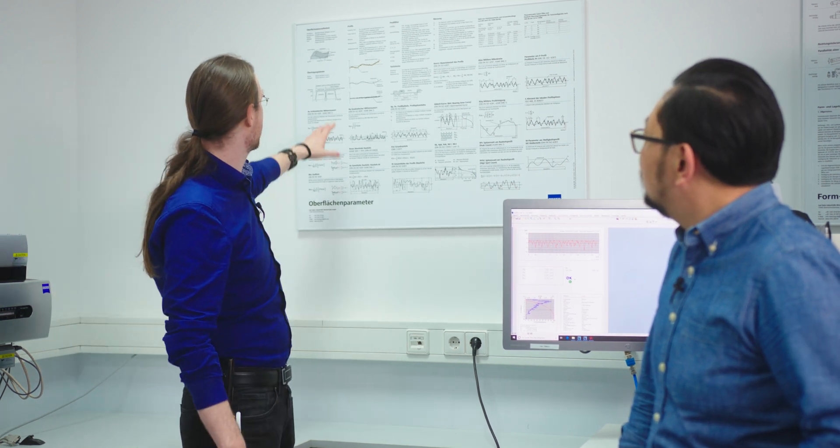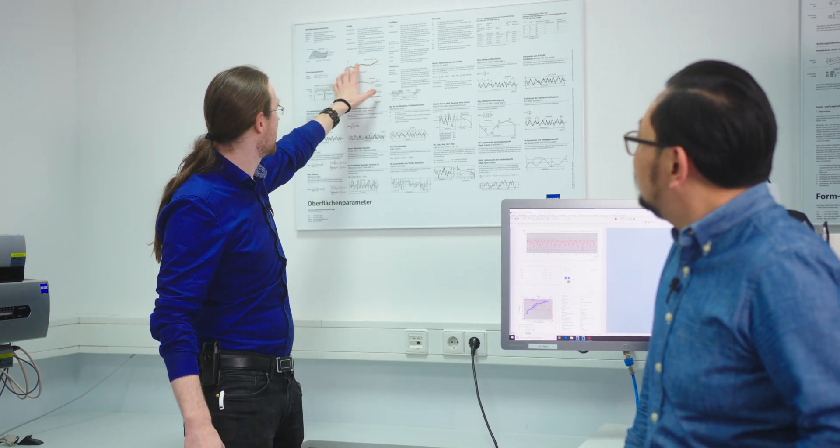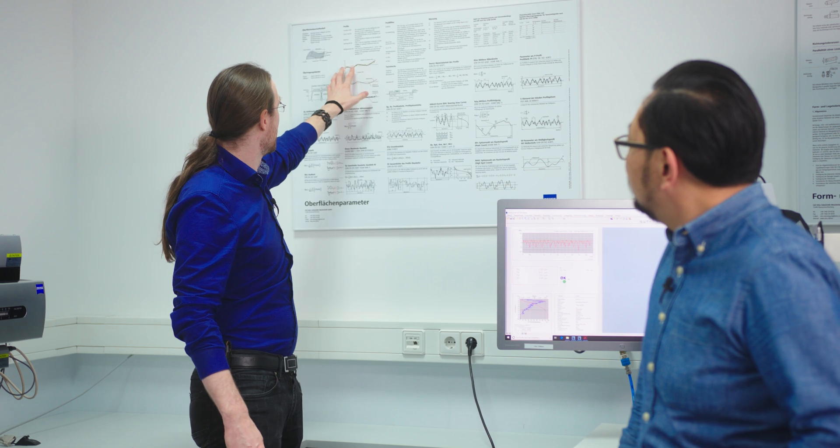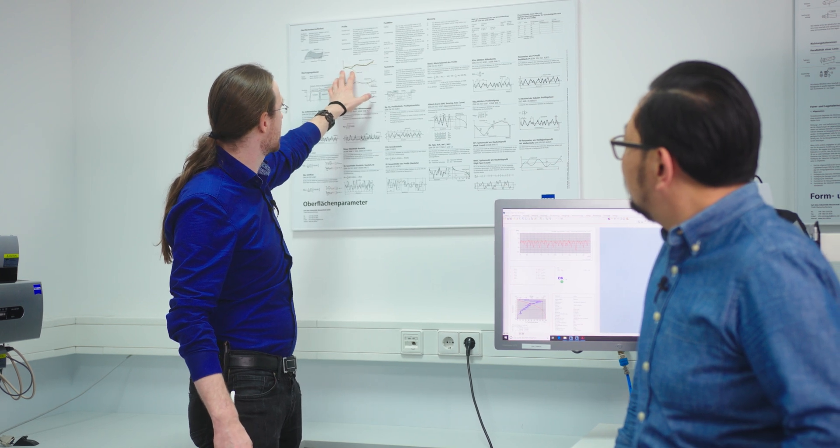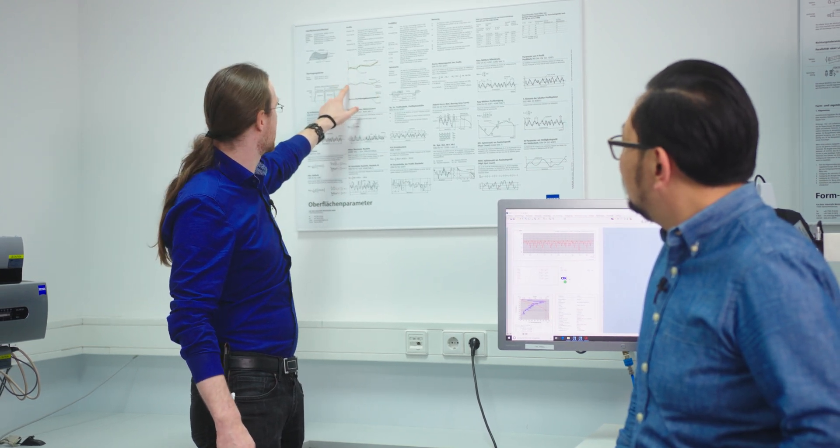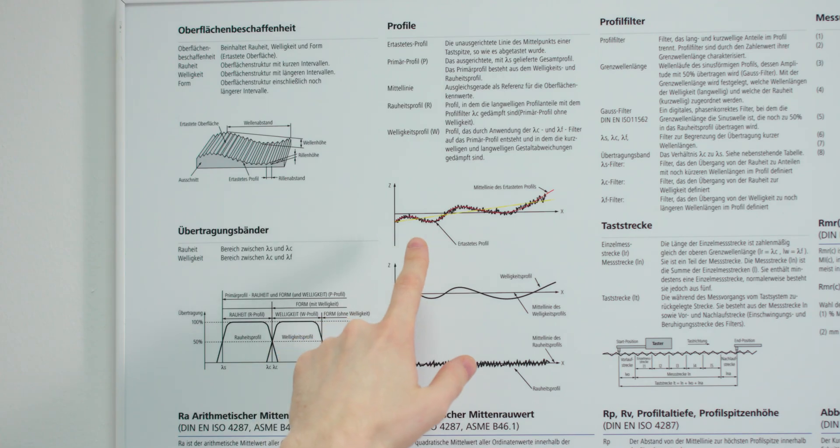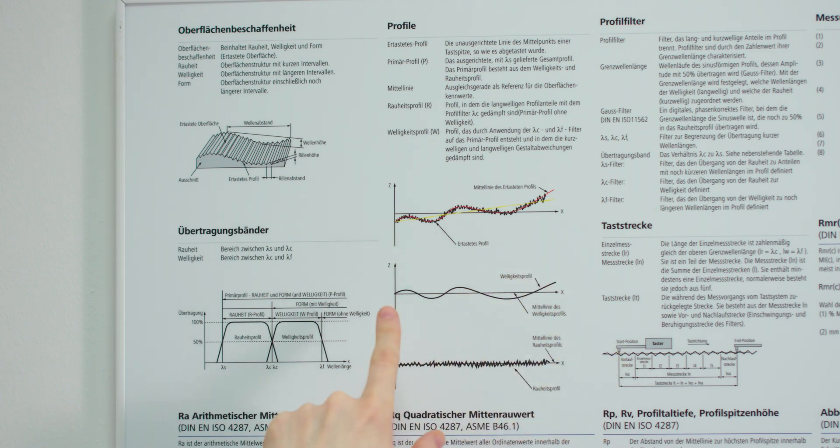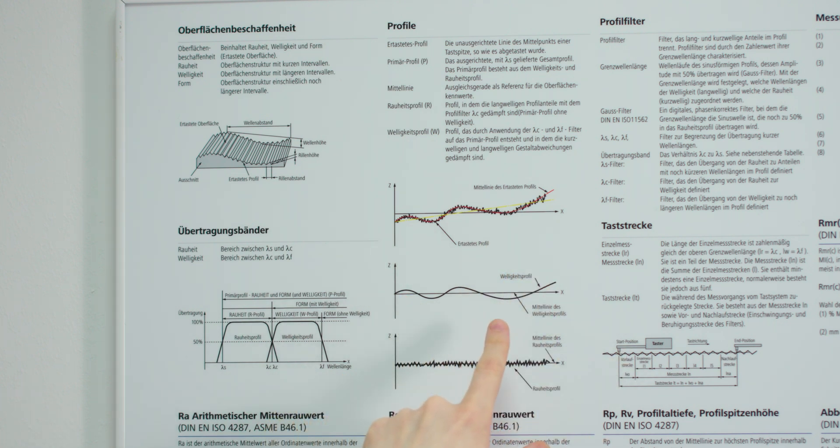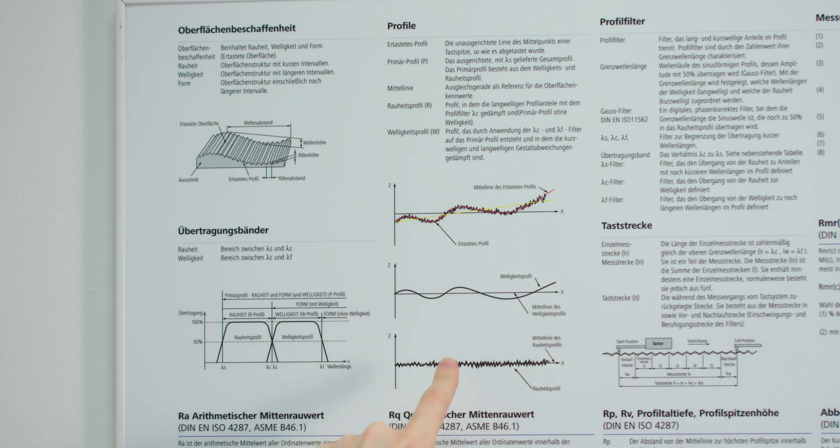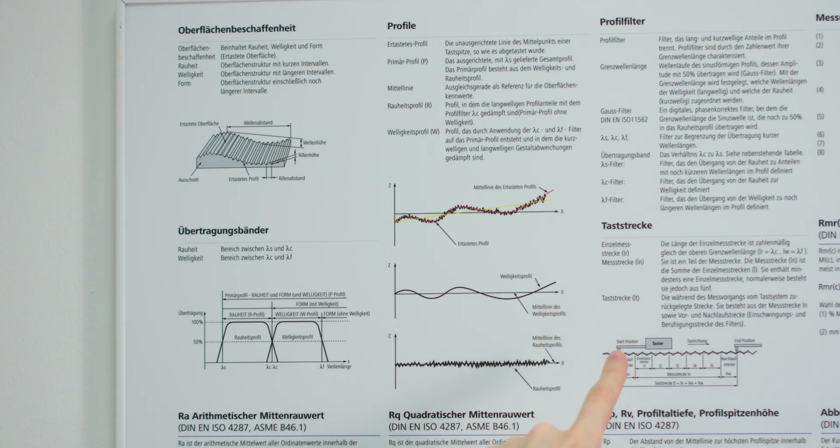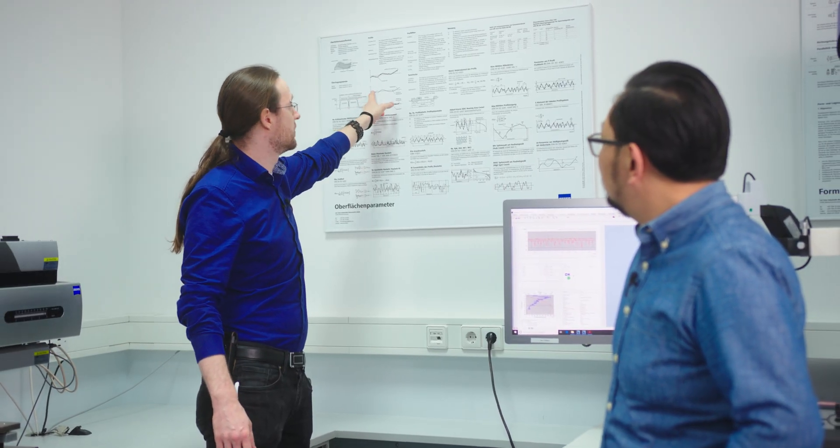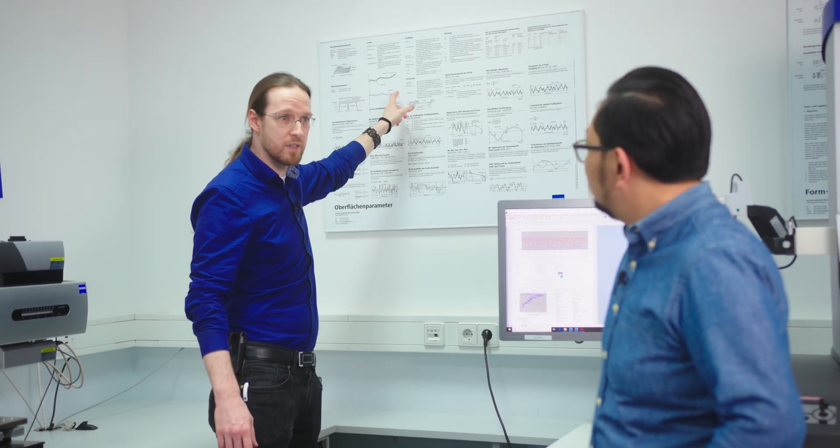So that means you have a trace profile like this here. And with different filtering settings you can make a waviness profile or roughness profile or maybe form profile. So that means you exclude from waviness the roughness or the form, and from roughness profile you exclude the wavinesses so that you have the possibility to analyze different types of wavelengths.